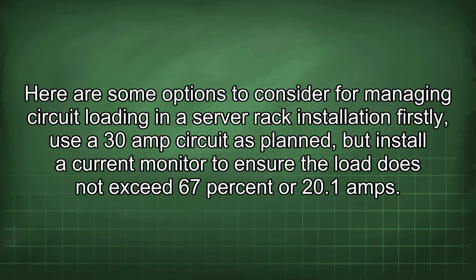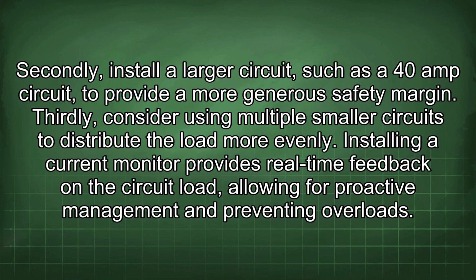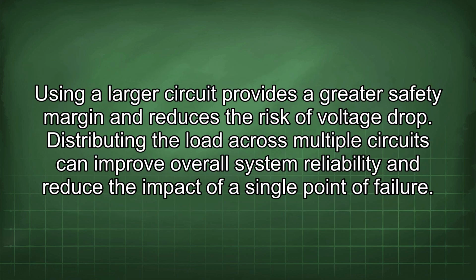Here are some options to consider for managing circuit loading in a server rack installation. Firstly, use a 30 amp circuit as planned, but install a current monitor to ensure the load does not exceed 67% or 20.1 amps. Secondly, install a larger circuit, such as a 40 amp circuit, to provide a more generous safety margin. Thirdly, consider using multiple smaller circuits to distribute the load more evenly. Installing a current monitor provides real-time feedback on the circuit load, allowing for proactive management and preventing overloads. Using a larger circuit provides a greater safety margin and reduces the risk of voltage drop.